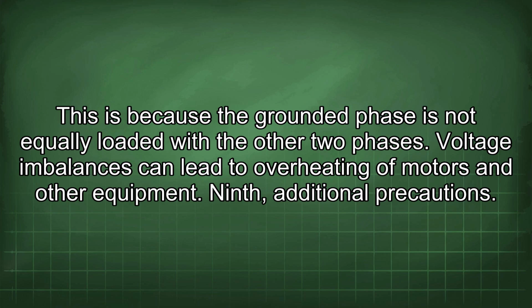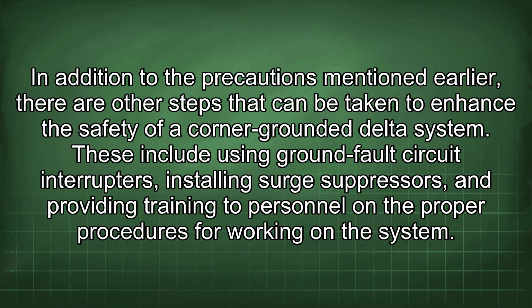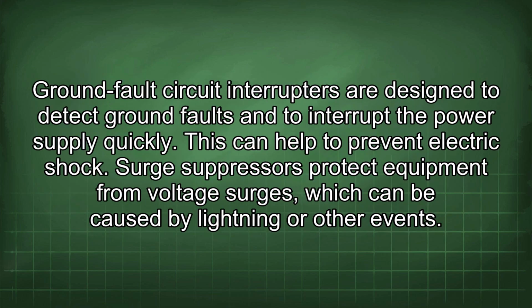9th, additional precautions. In addition to the precautions mentioned earlier, there are other steps that can be taken to enhance the safety of a corner-grounded delta system. These include using ground fault circuit interrupters, installing surge suppressors, and providing training to personnel on the proper procedures for working on the system. Ground fault circuit interrupters are designed to detect ground faults and to interrupt the power supply quickly. This can help to prevent electric shock.